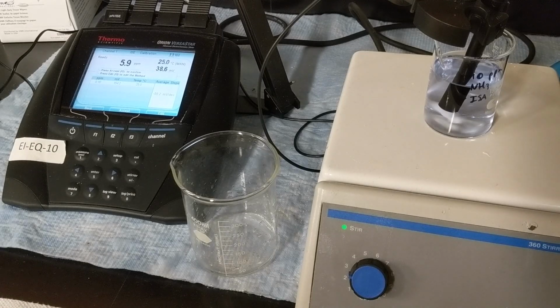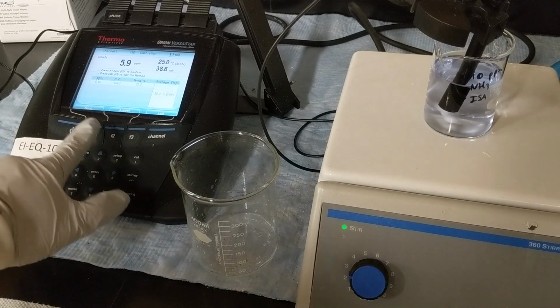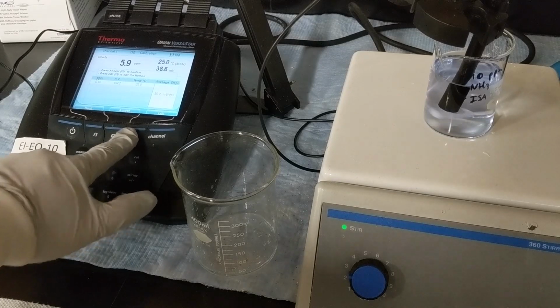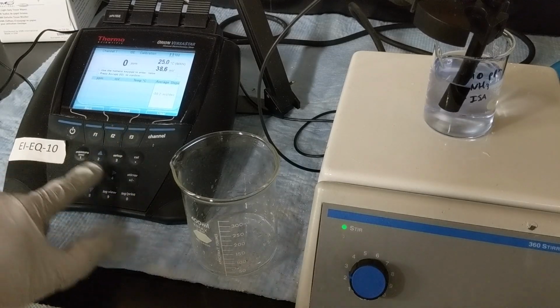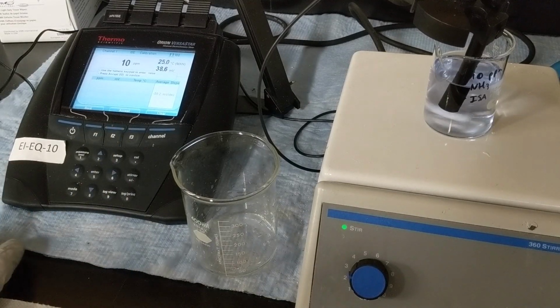It's low, right, but actually not super surprising because my 0.1 was reading at 0.05, so about half, and this one is reading a little bit above half of what it should. So now, again, instead of hitting accept, I'm going to hit edit and tell this that this is a 10 ppm sample, and then hit accept.